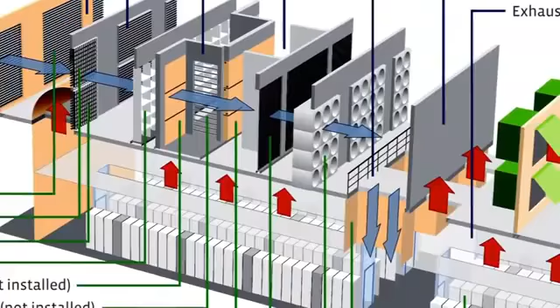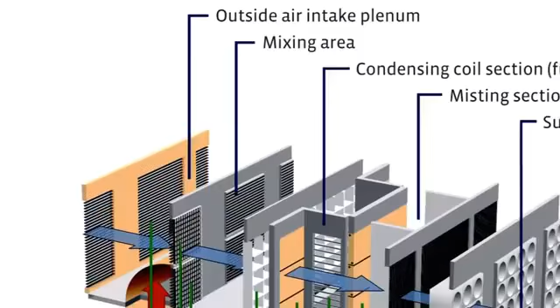The air comes in on that end of the building, moves this way, and then goes down - each room is a stage in the process. Starting at this end, where it's coming into the building: the main feature from a cooling standpoint is outside air, which comes in through this grill. You can see movable dampers behind you - air rolls in, goes through those dampers, and goes through a succession of stages where we mix, filter, and cool it before sending it down into the data center. On really cold days, you don't want really cold air.